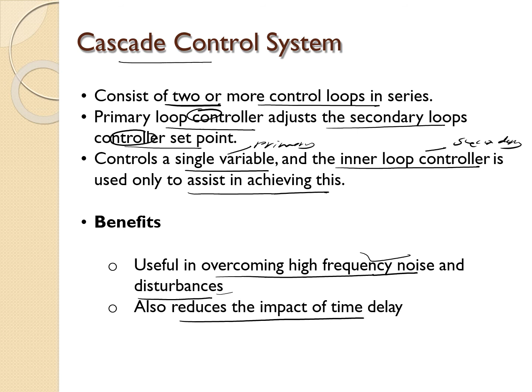So a cascade control system controls a single variable, and the inner loop controller is used only to assist in achieving this. That means this one is primary, this one is secondary. The benefit of this cascade control system is that it is useful in overcoming high frequency noise and disturbances, and also reduces the impact of time delay. So basically the benefit is the same as feedback plus feed forward, but it is very useful for high frequency noise and disturbance. We can say that it can be used for dynamic systems, fluctuating processes or unstable processes.